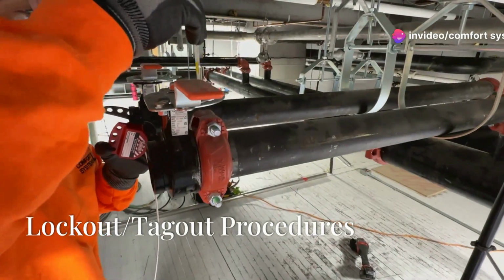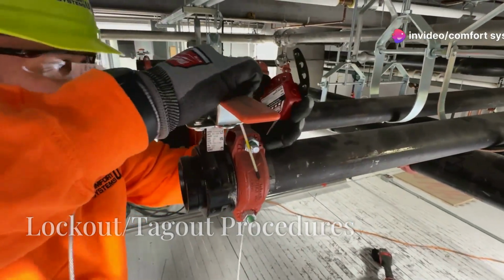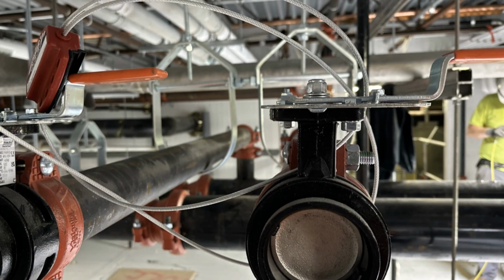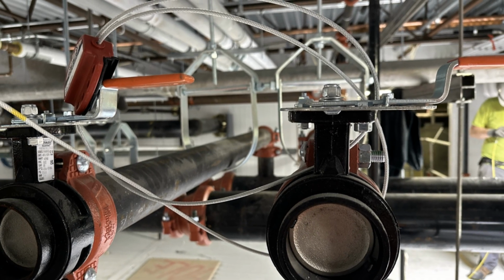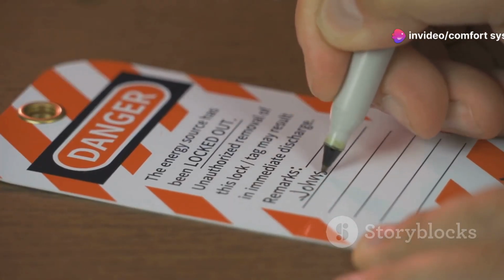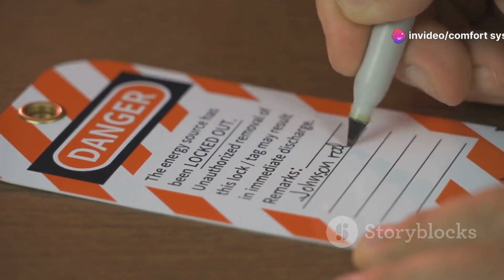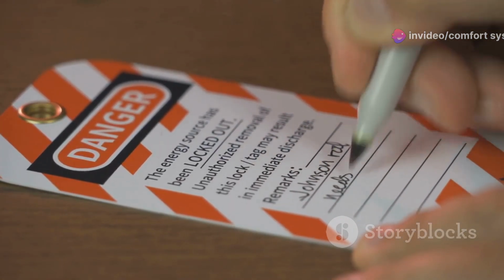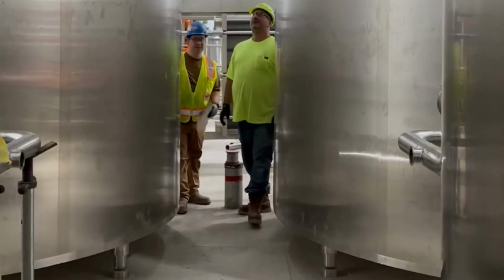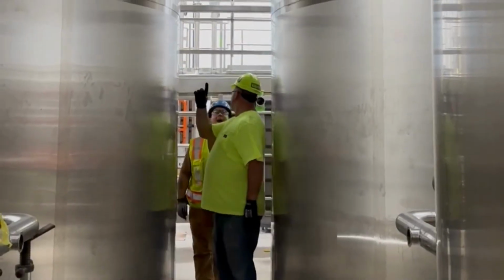Step 4. Service and/or isolation valves shall have the appropriate lockout/tagout devices installed, and locks shall be applied by each employee who is involved in the pressure testing. After all tags and lockout/tagout devices have been installed, 2 trained competent employees must sign off that the procedures have been met. By signing off, employees are confirming the system is ready to be pressurized.